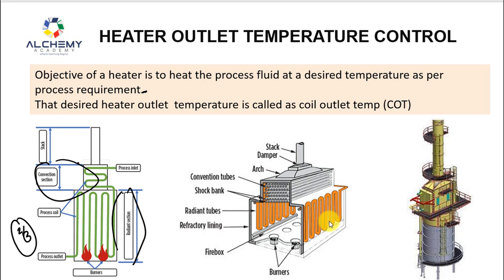Apart from visual monitoring, safety system interlocks are incorporated into the heater and we take action as per emergency conditions. A damper controls excess oxygen; for natural draft heaters it is kept around 80–90% open based on requirement. The stack takes combustion gases to the environment. We also continuously monitor SOx, NOx, and SPM parameters per CPCB government regulations, and if there is a deviation we report it and calibrate the instruments.